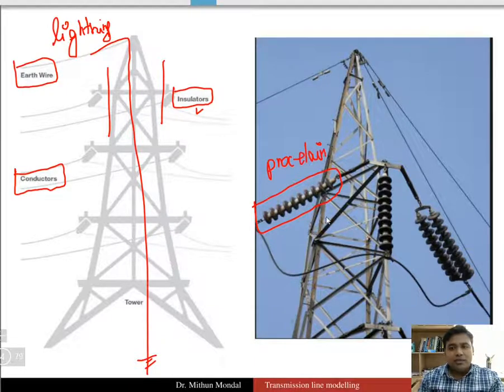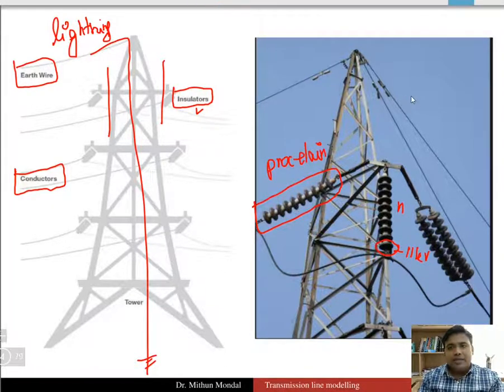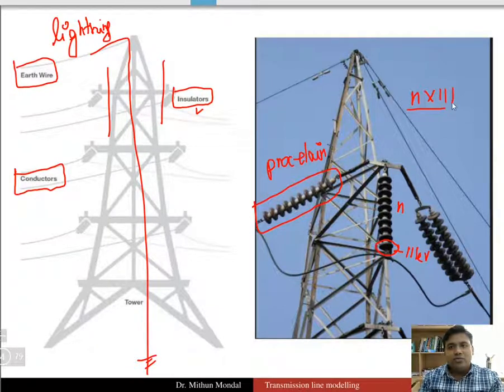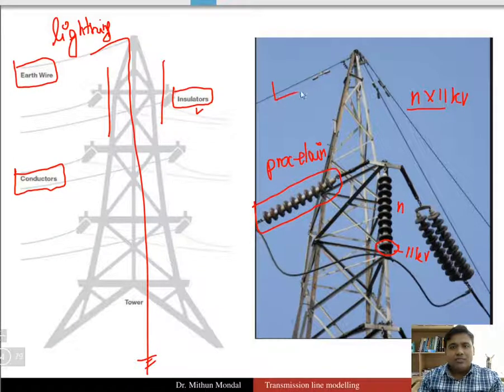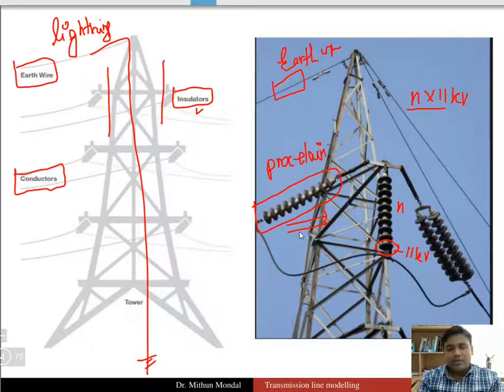A porcelain insulator is used for this transmission line. Each disc of a porcelain insulator represents 11 kV, so if there are n number of insulator discs, you multiply n by 11 to get the transmission level voltage. The conductors run through the line but are not perfectly straight — they are a little bit bent.